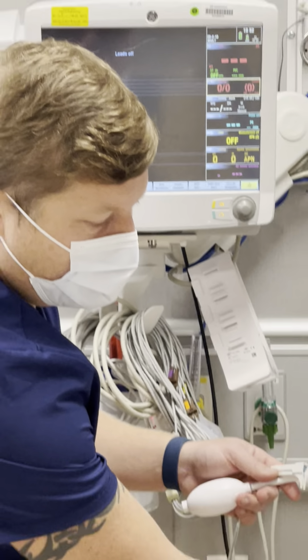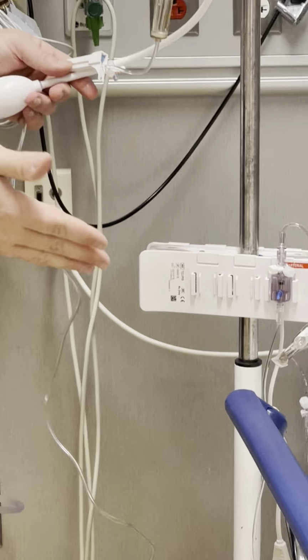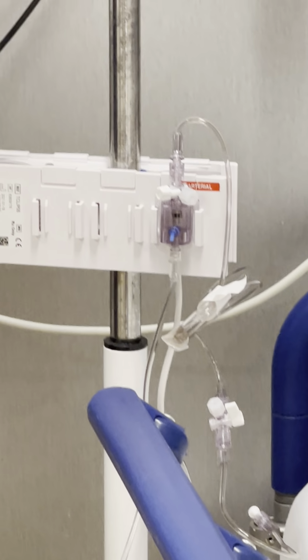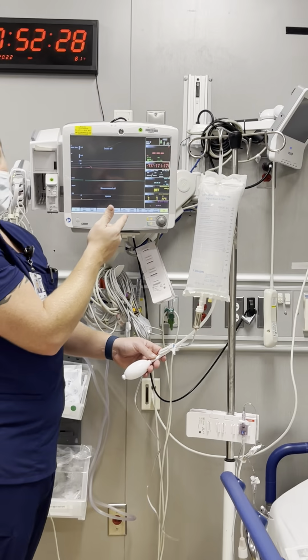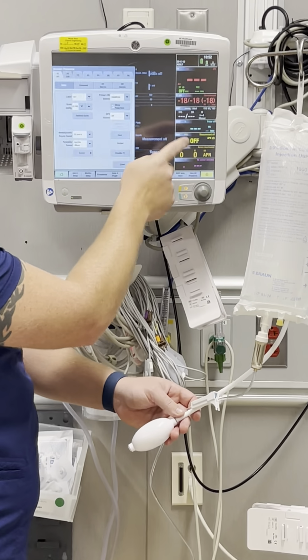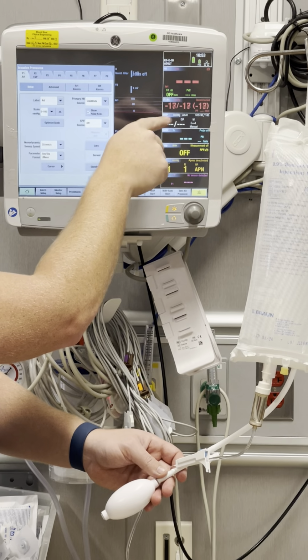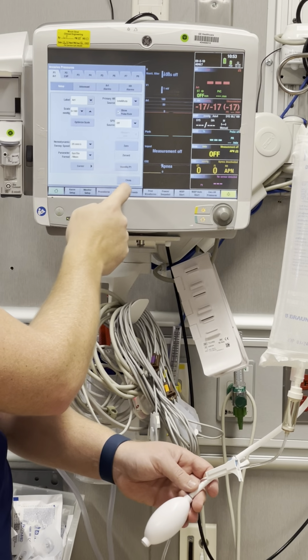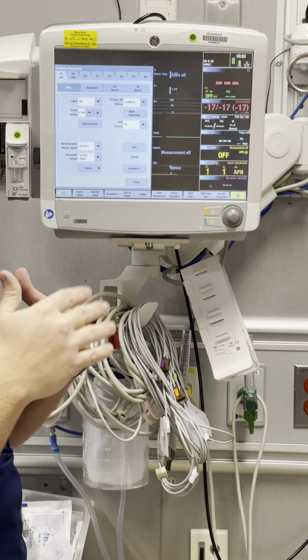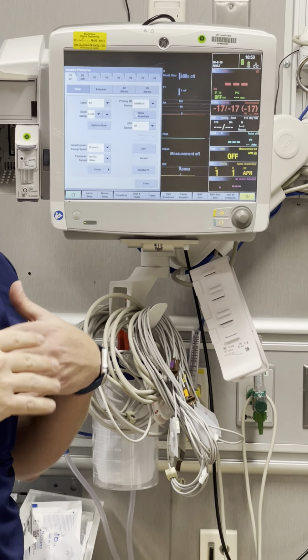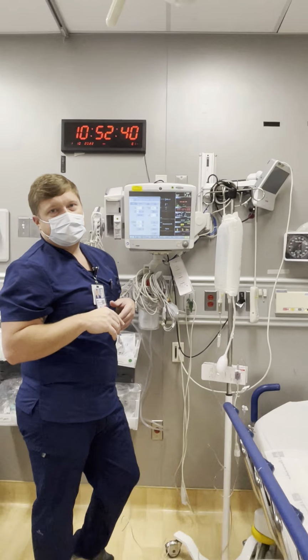You could then open it up all the way. The whole entire system's open up to the patient, and if it's hooked up to an actual patient, you'll begin seeing a waveform. Once that baseline waveform appears, if you click on your pressure again, you can hit optimize scale, and that will make sure the scale is optimized to your patient's actual pressure at that time. That's good.